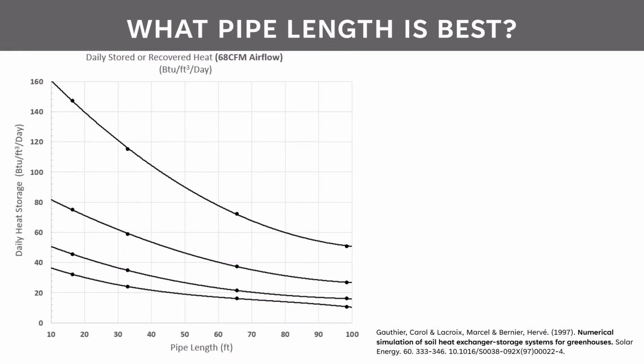This graph was also produced by the same study as the previous one. However, now we have the length of the pipe on the bottom axis and the daily heat storage rate on the vertical axis. The airflow rate is held constant at 68 CFM, and the pipe-to-pipe spacing is shown by each line. The recommended 16-inch pipe spacing is shown in green.